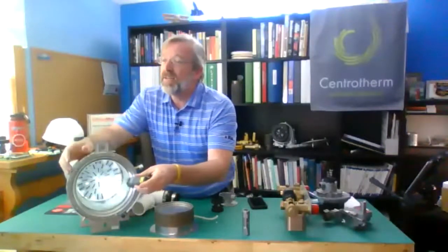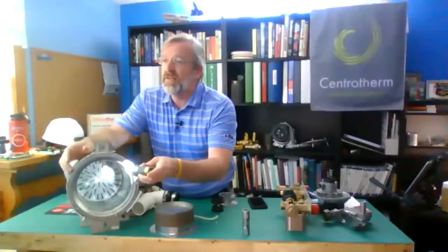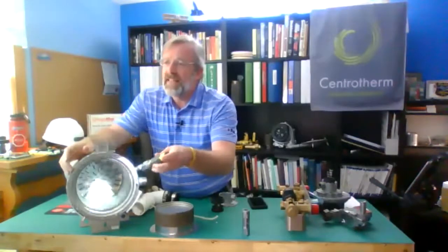When we're looking around in here, as we look at it, this one's in pretty good shape. Always looking for hot spots, anything like that. We certainly don't want to see any of those. And then we're looking for any buildup around those openings. If I've got some, I'm going to spend a little extra time scrubbing that out. That could even be as simple as I might not have to scrub it. I could actually just spray that in a spray bottle. I could really spray that vinegar right on that area, and that's probably going to do a good job of getting that cleared out for me.